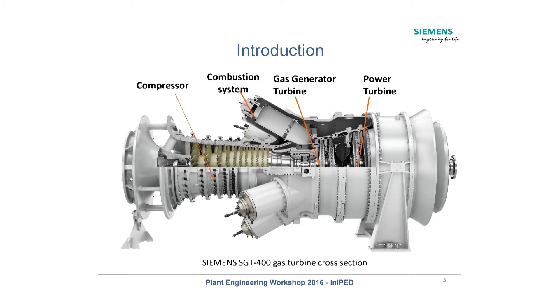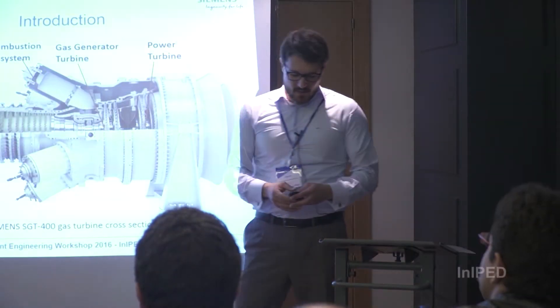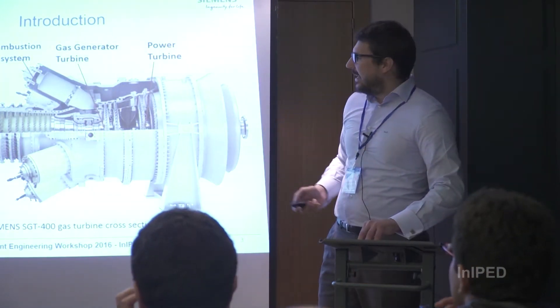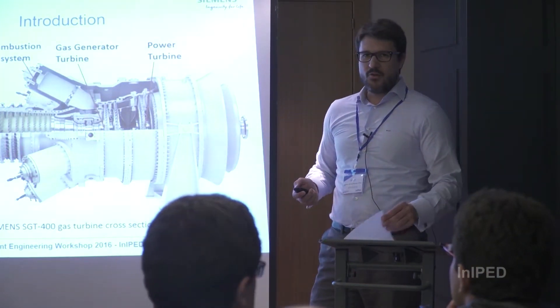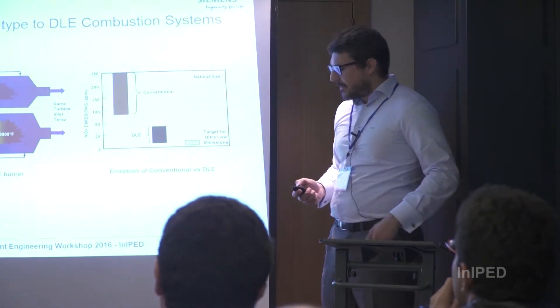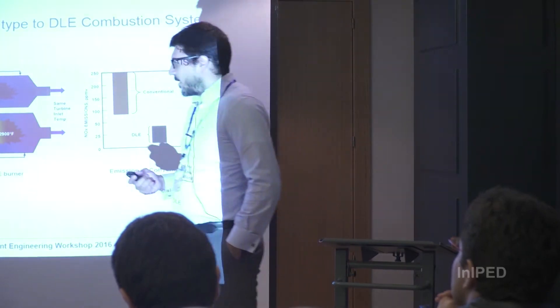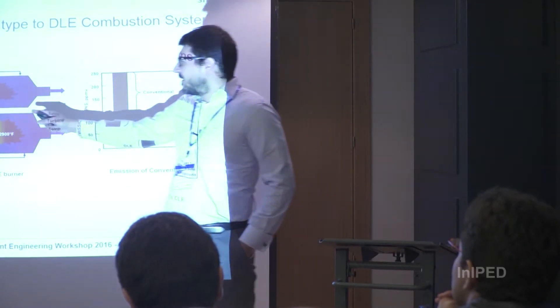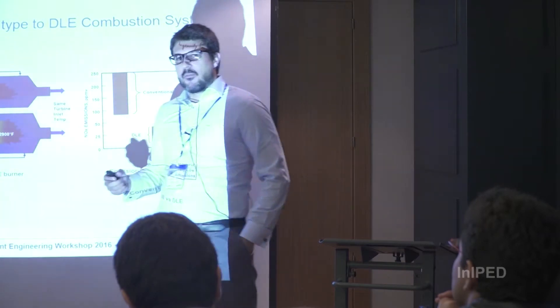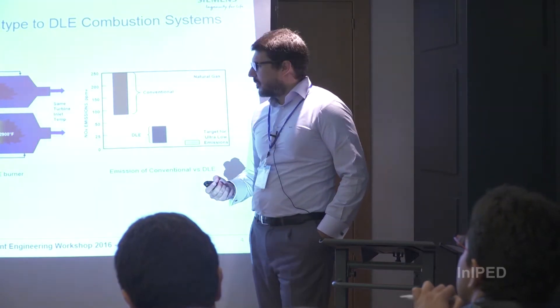The combustion system withstands the highest pressures and temperatures in our system, so it is very critical not only to select proper materials, but even more critical to select the right cooling in this area. Peak temperatures are highly related to NOx generation. The phenomenon that occurs is that we normally reach peak temperatures and have what we call thermal NOx formation.